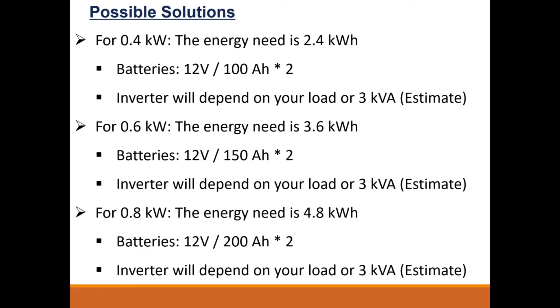If we look at the scenario, from 100 we move to 150, we move to 200 amp hour in sizes of 2. From our experience, you can go for a 3 kVA system, which can handle most residential loads, provided there is no additional water pump involved. Of course this is an estimate from our experience, so you also need professional consultants to determine the custom system that you need.